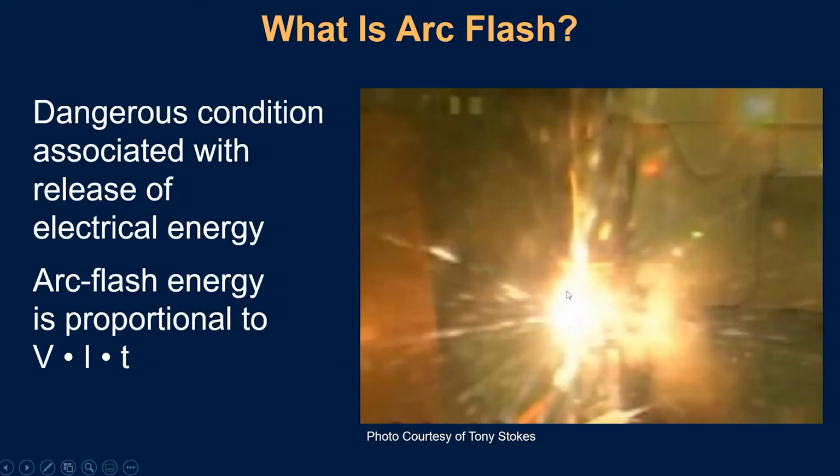And that rapid ionization causes so much heat that it can expand metal, blow out shrapnel, and cause all sorts of damage. In fact, an arc flash produces pretty much the hottest temperatures that you'll see on Earth, with temperatures going up to 35,000 Fahrenheit. And just in relative terms, electric arc furnaces used in steel making can have temperatures that touch 5,000 Fahrenheit in comparison.